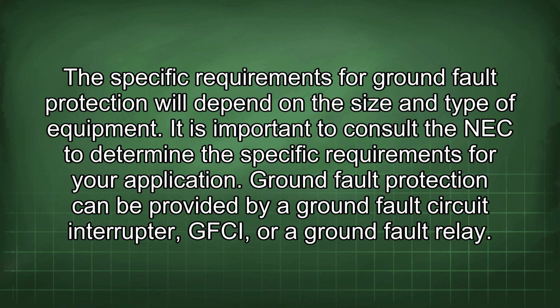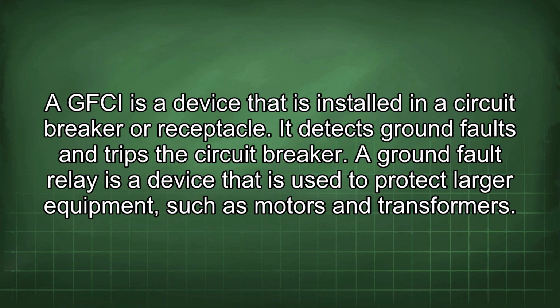Ground fault protection can be provided by a ground fault circuit interrupter, GFCI, or a ground fault relay. A GFCI is a device that is installed in a circuit breaker or receptacle. It detects ground faults and trips the circuit breaker. A ground fault relay is a device that is used to protect larger equipment, such as motors and transformers.